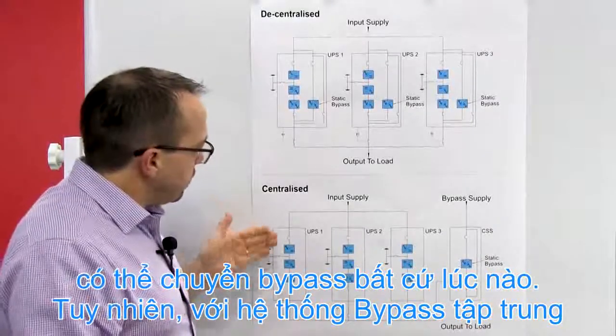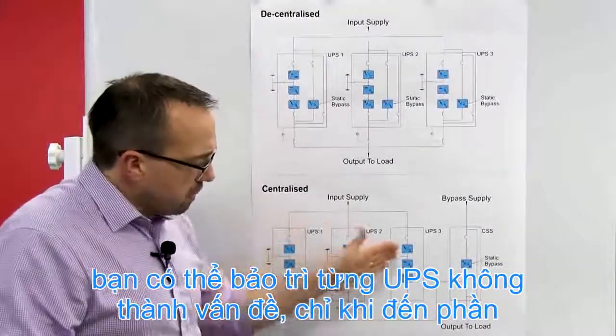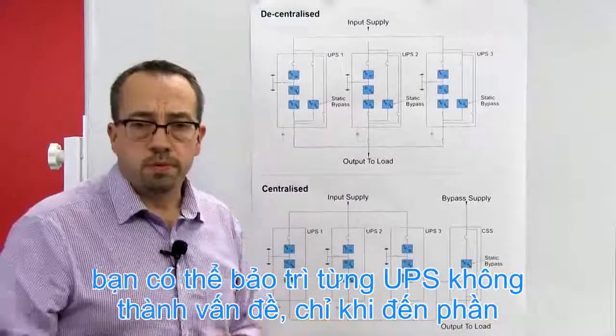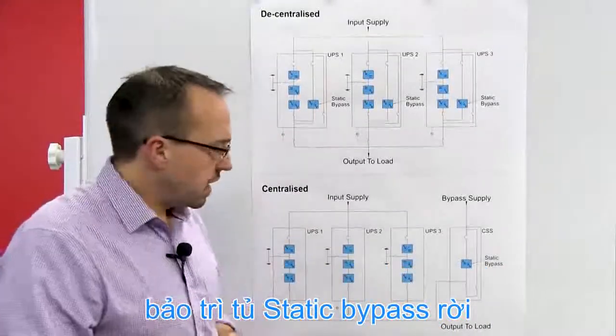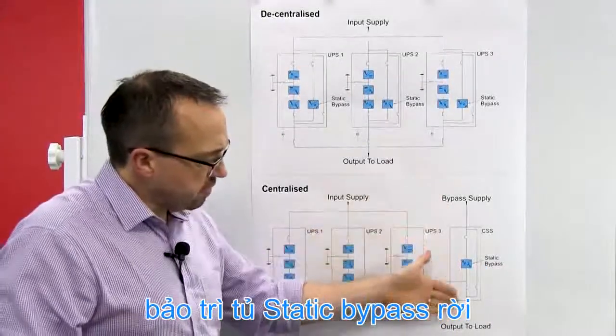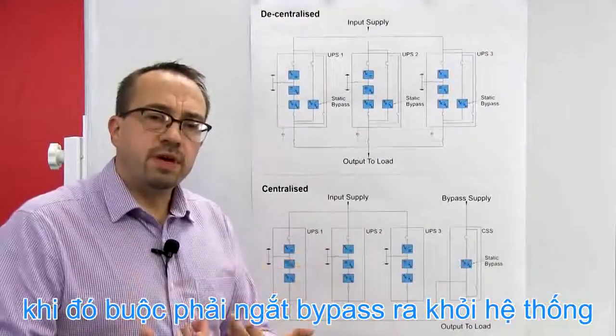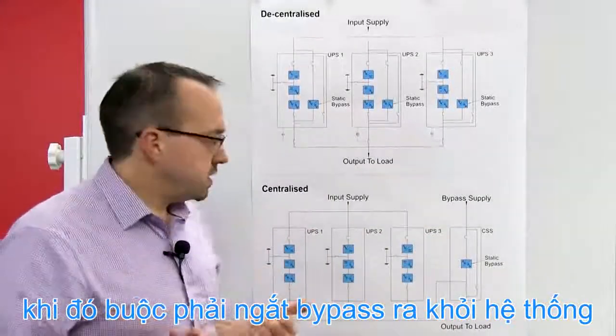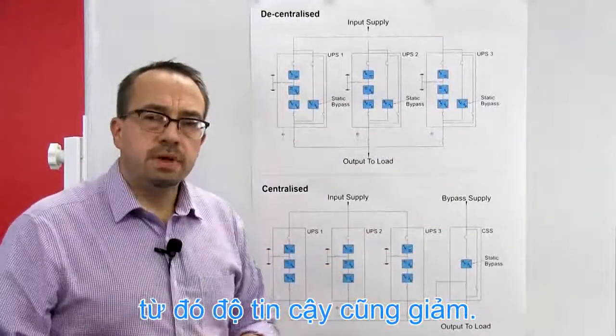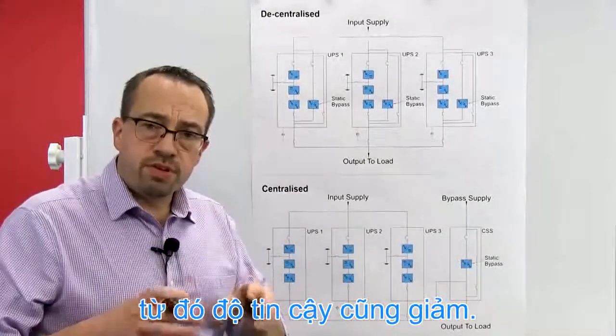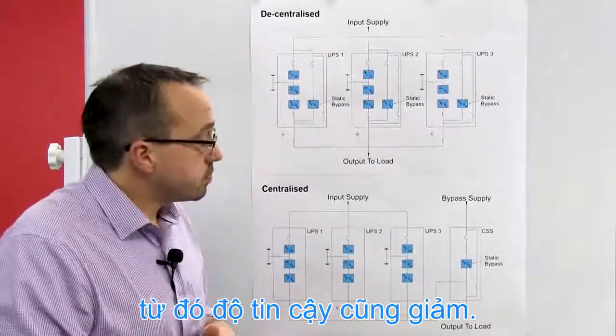Whereas with the centralized system, again, you can maintain the UPS modules with no problems whatsoever without dropping resilience. However, when you need to maintain the static bypass module, you're effectively removing the bypass availability to all of the UPS system, and hence during maintenance the resilience level is reduced.